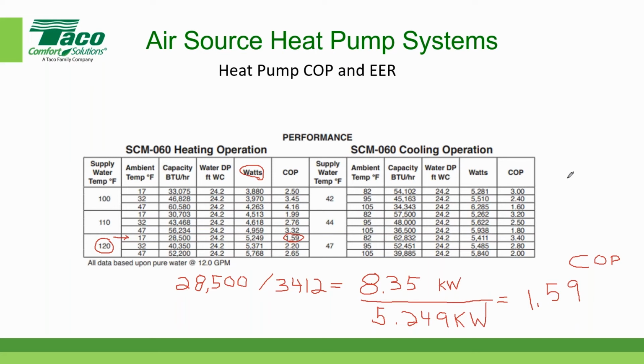Okay, so let's take a look at the chart on the heating side. Look what happens to an air to water heat pump as the ambient temperature goes up. See how it goes from 17 to 32 to 47? Look what happens to the COP. The COP also goes up. See that? Now that makes sense.